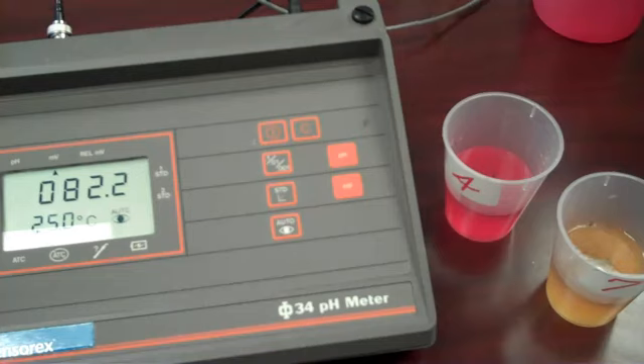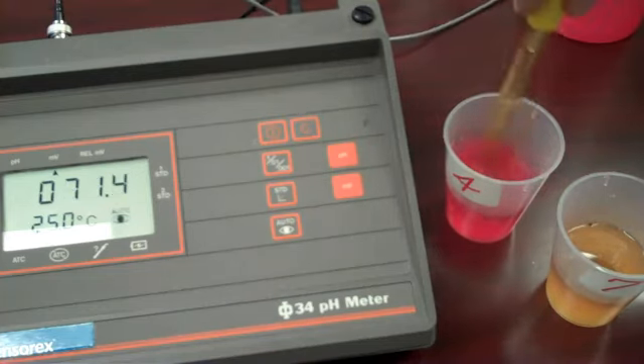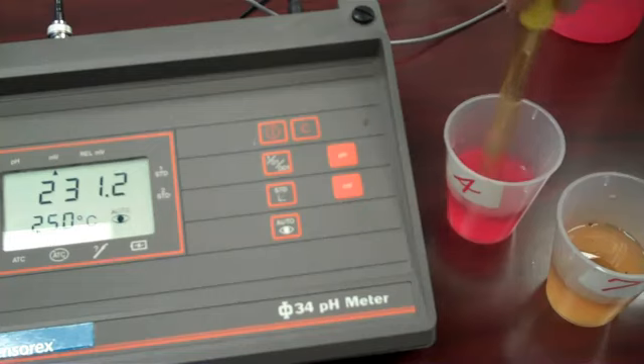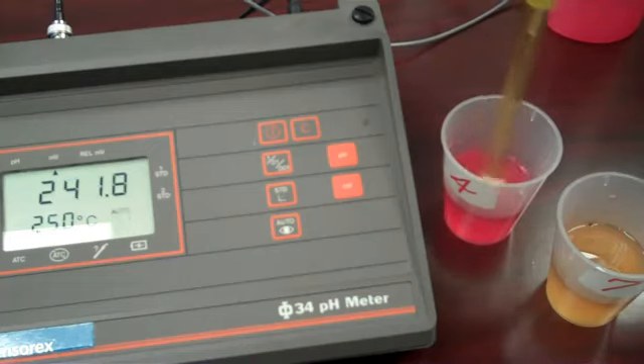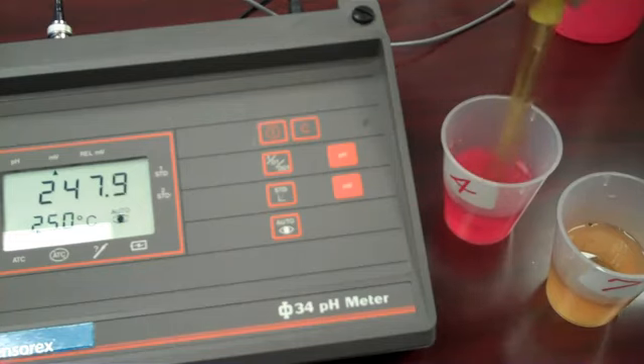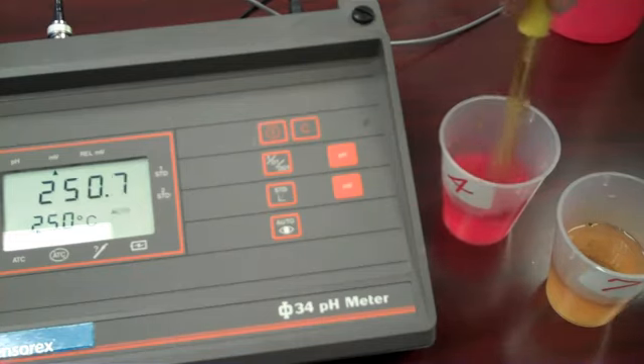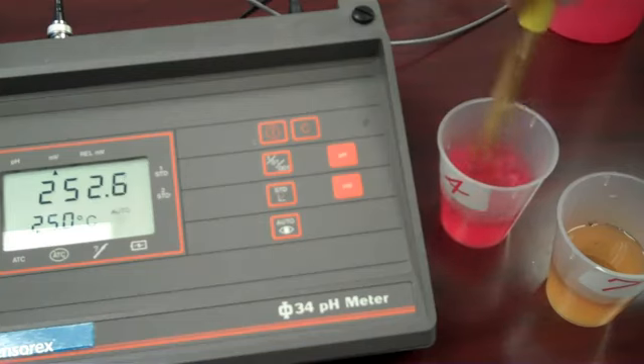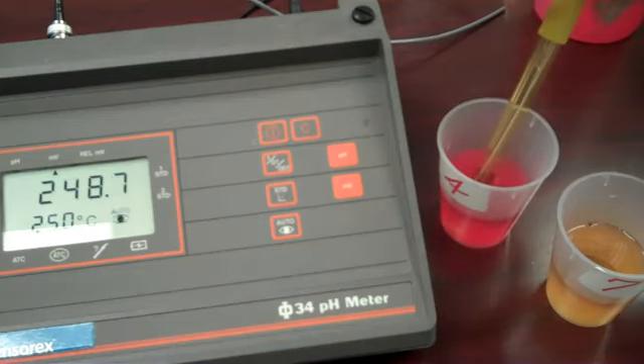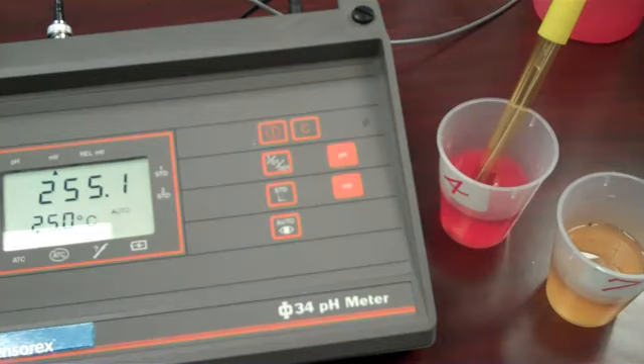Do a second check, rinsing the electrode in rinse water, and then place the ORP sensor into the quinhydrone saturated number 4 buffer. The number 4 buffer should have an ORP value of something close to 250 millivolts, plus or minus 15 millivolts as tolerance. In this example, we're up to just over 252 millivolts. So we have a known good ORP electrode providing 2 points of calibration.